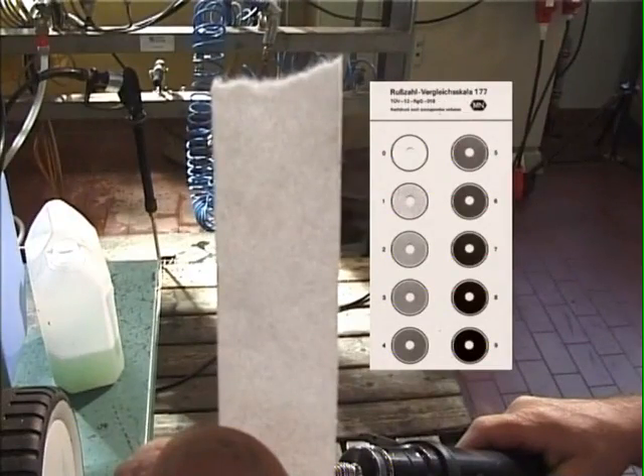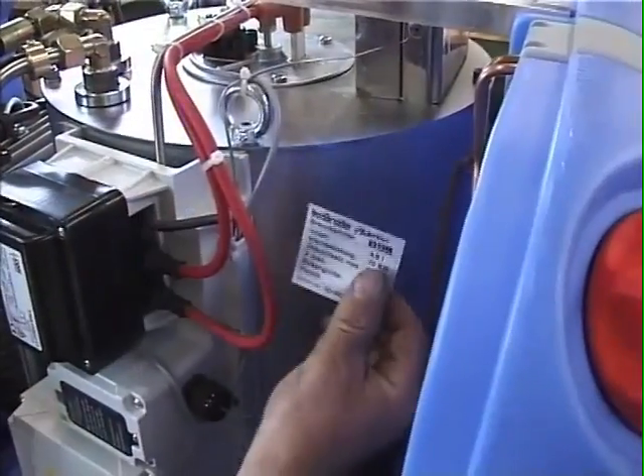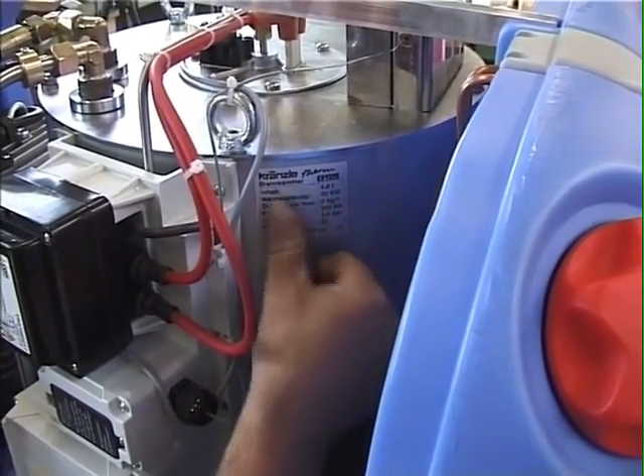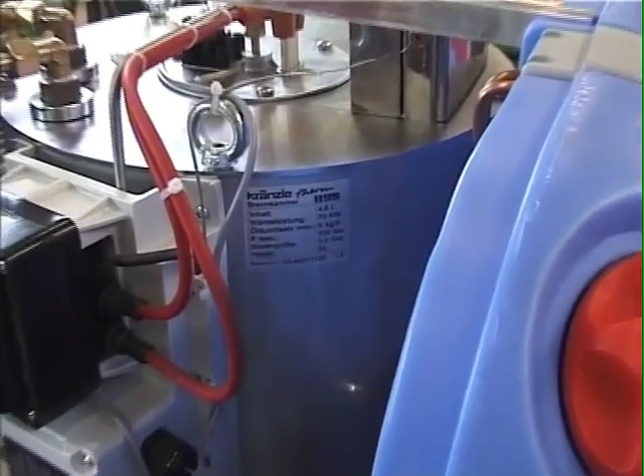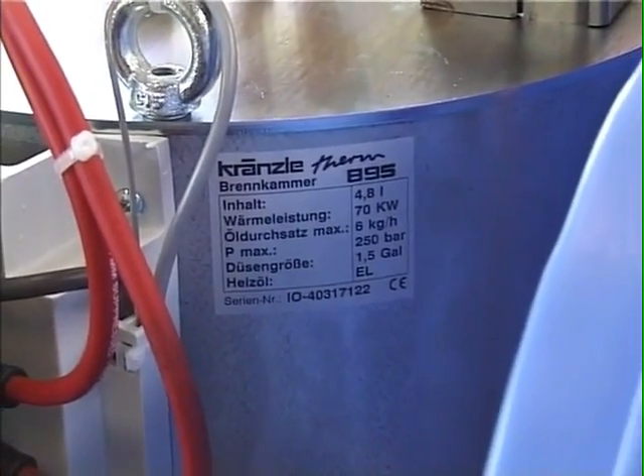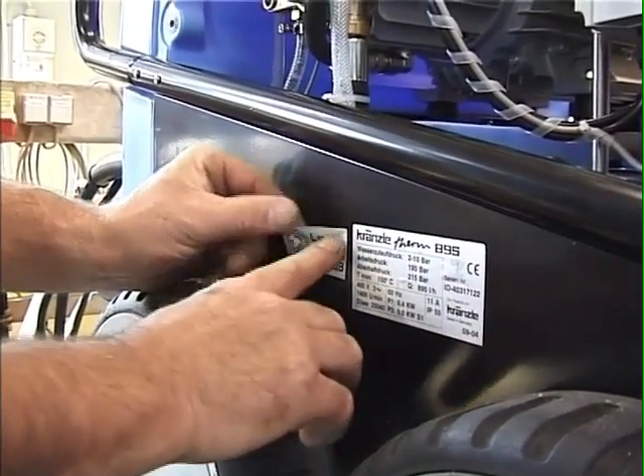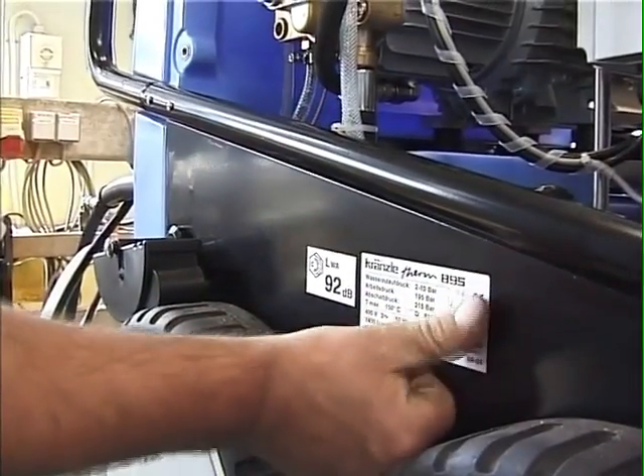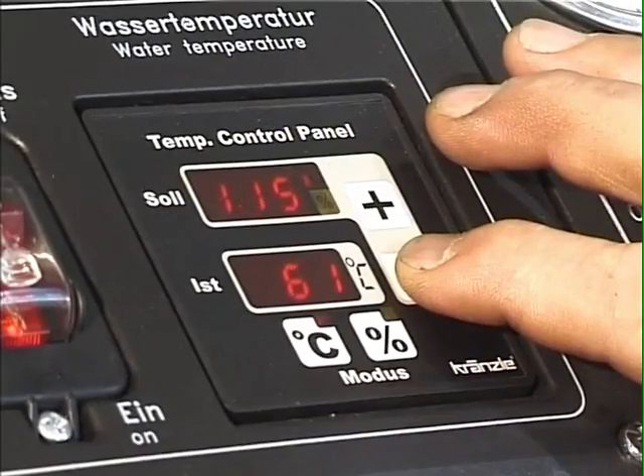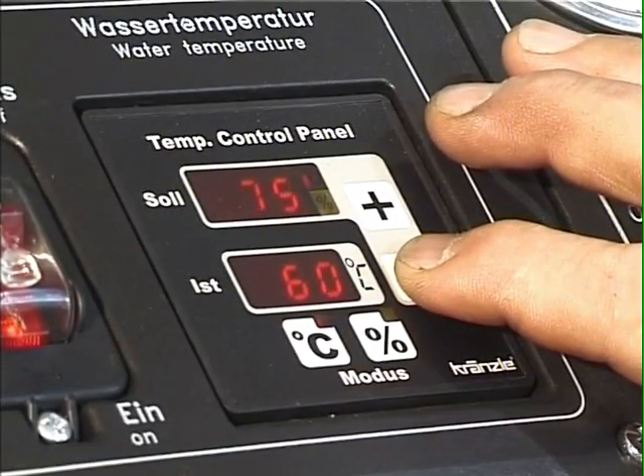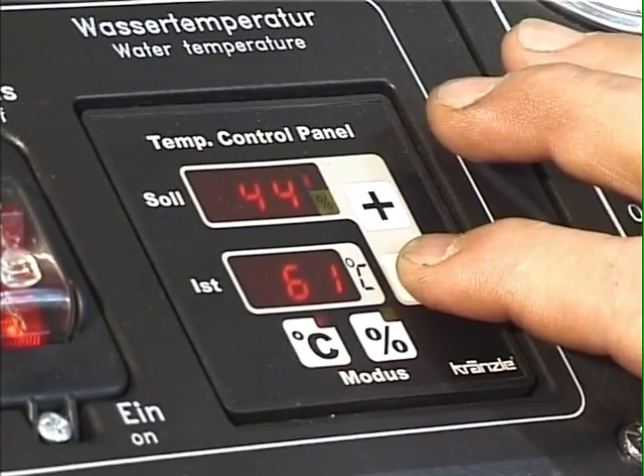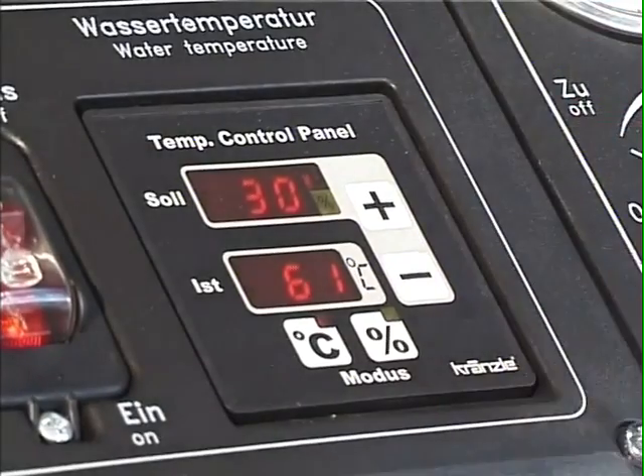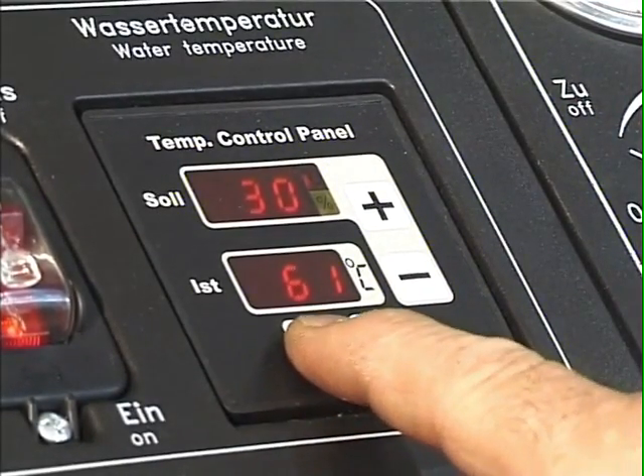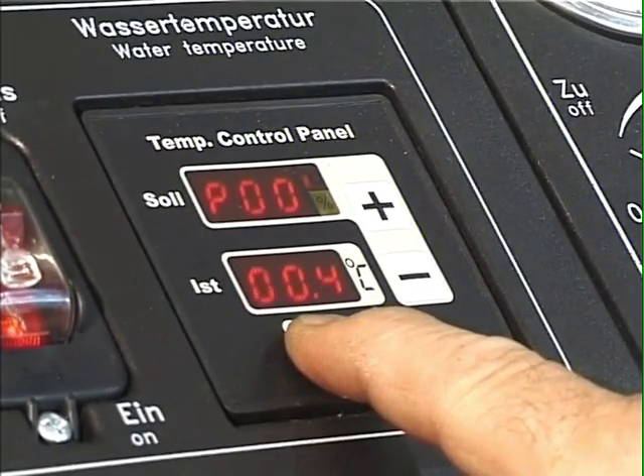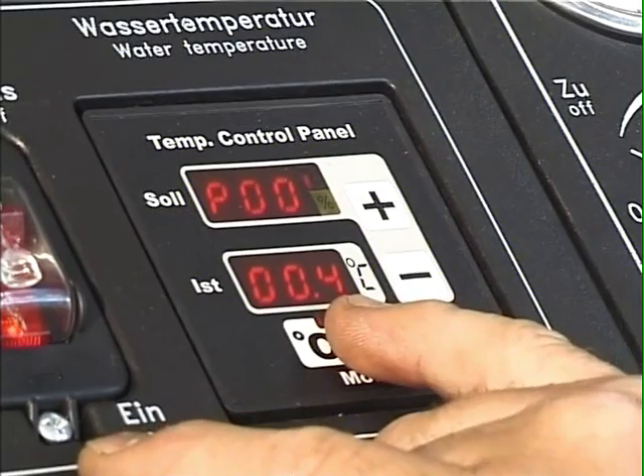Soot particles are measured. The result is compared with the values on this scale. After all these things have been done, the type plate is inserted with the machine-specific data and the serial number. The burner capacity and correct function of the thermostat and digital display on the control panel are checked. The operating hours of burner and pump can be displayed.